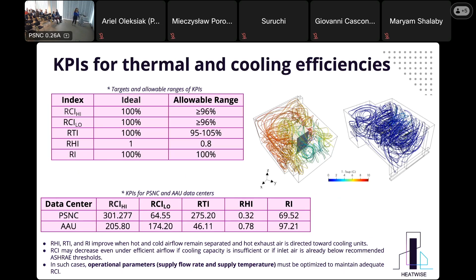For retrofitting of the PSNC data center, there was a cooling ventilation return very close to the cooling supply system, the air cooling systems. That means the cool air that you supply is almost sucked in by the ventilation return. So there was recirculation and bypassing of the cold air. We introduced the idea of adding a separator, and then trapping the cold air in the desired areas rather than the undesired areas.